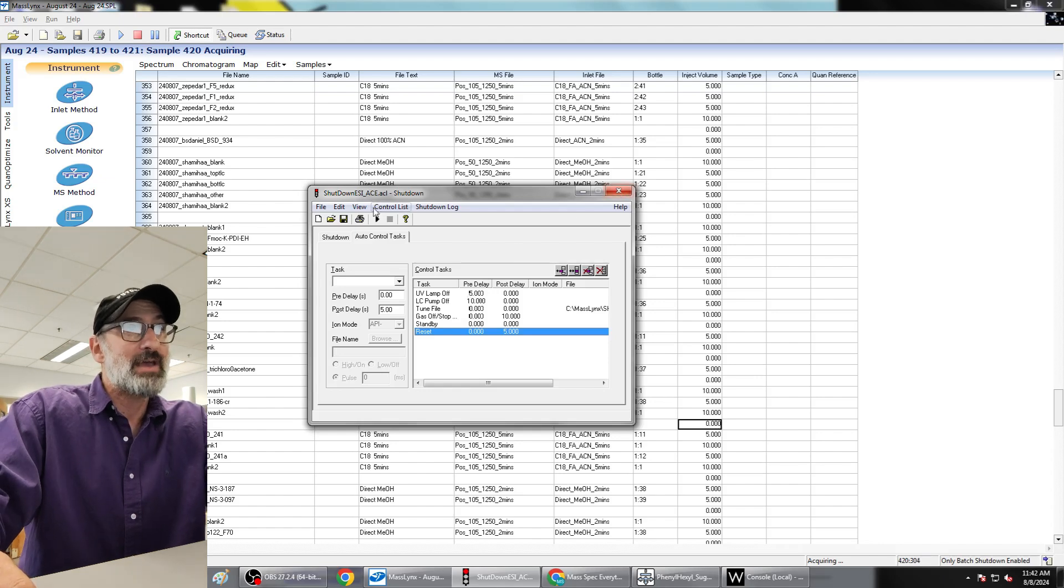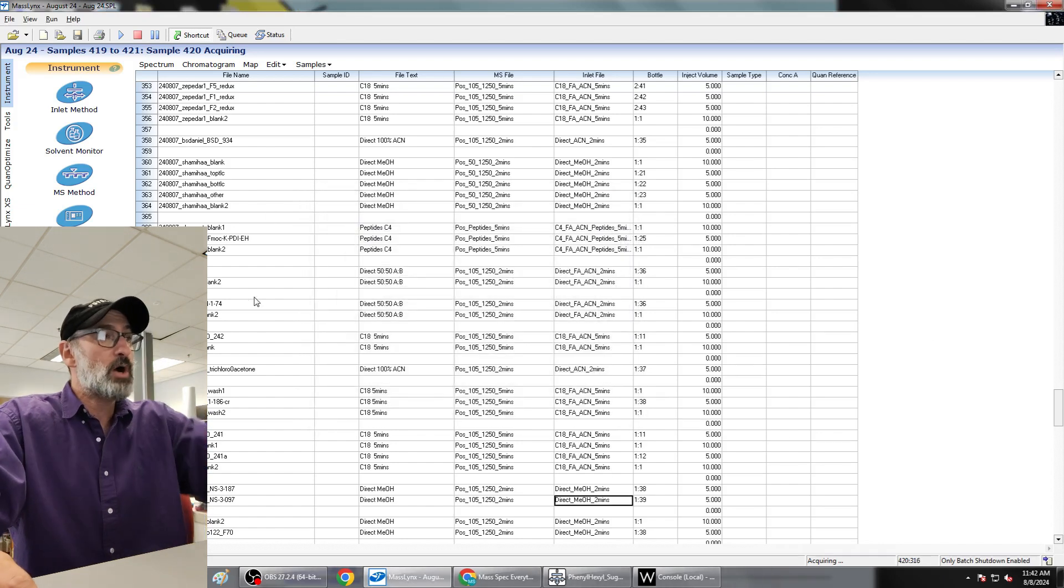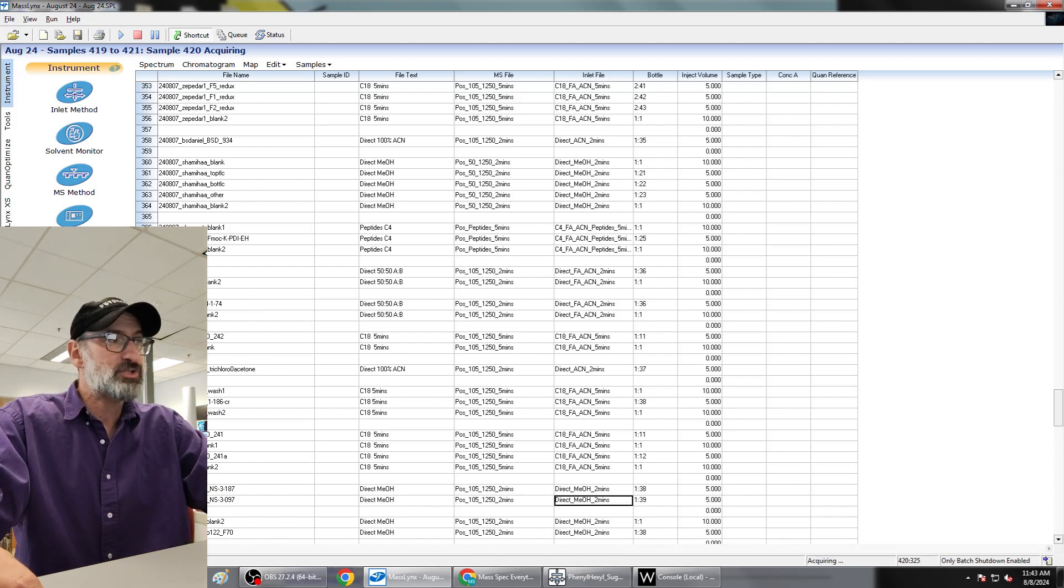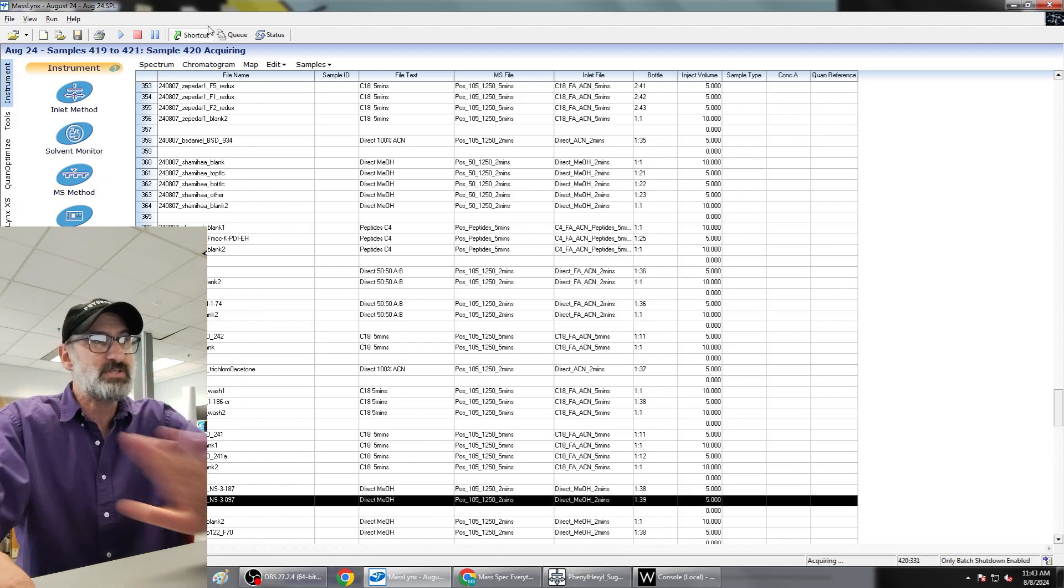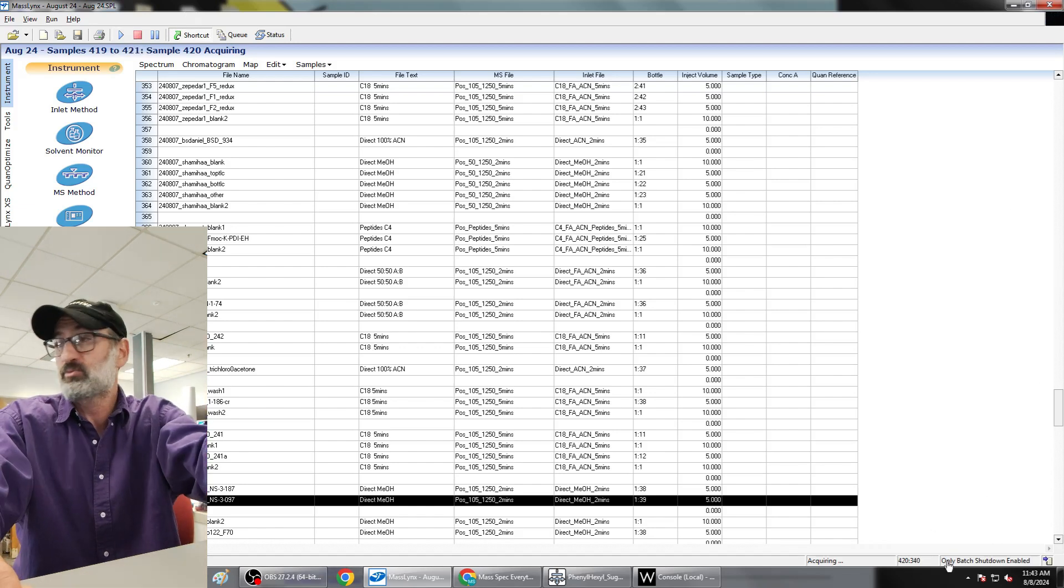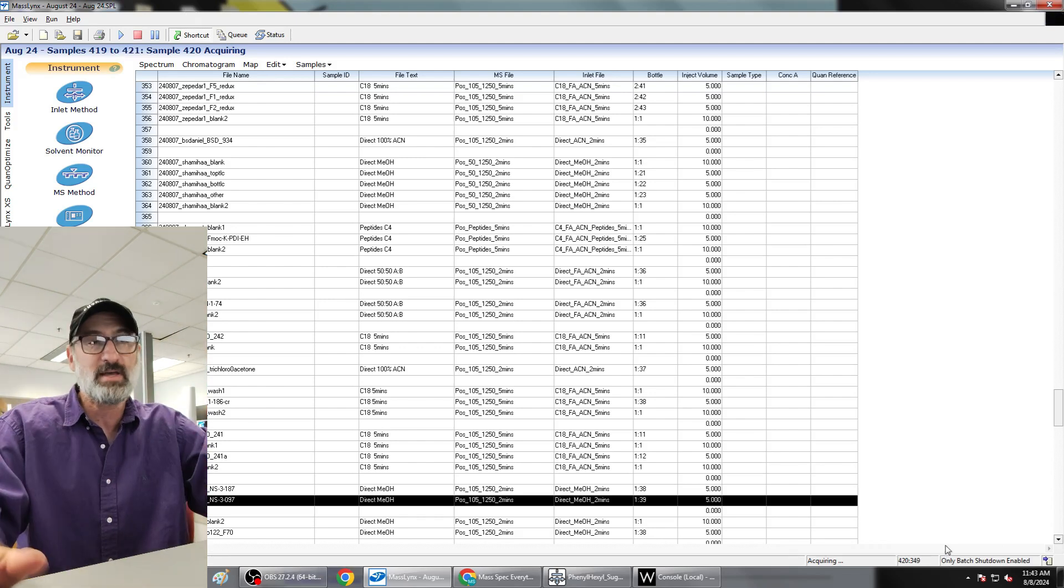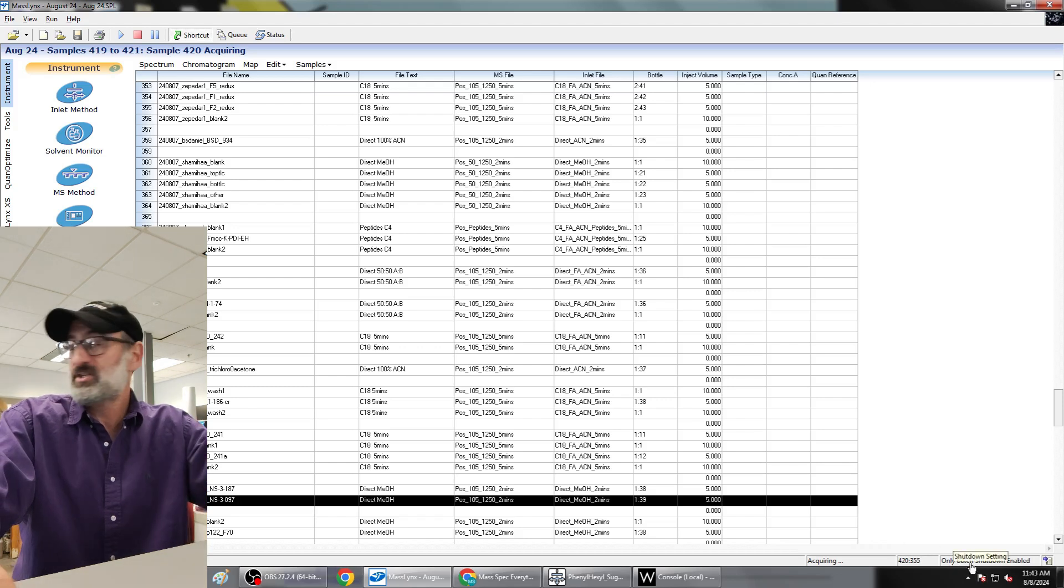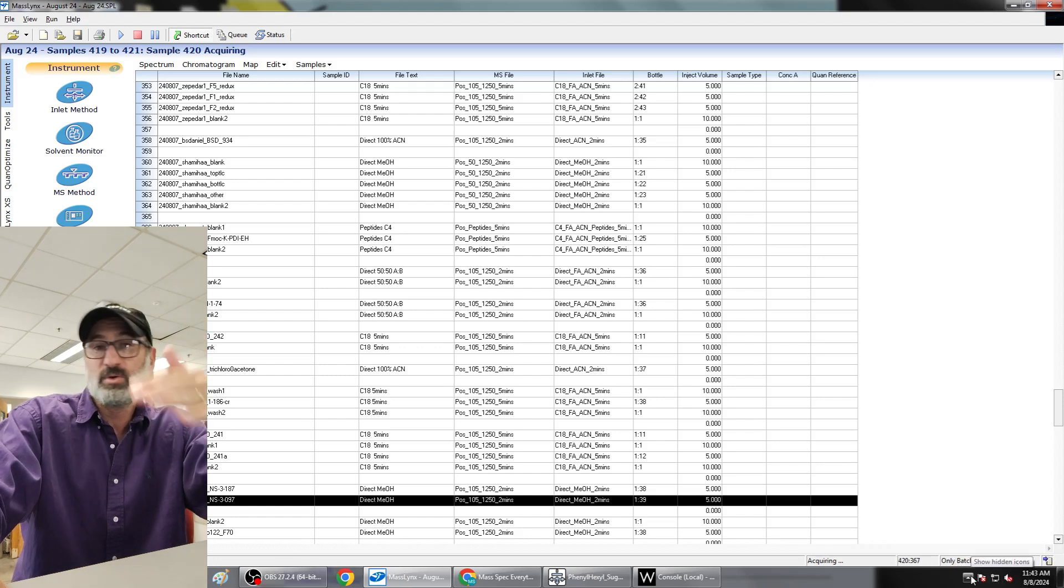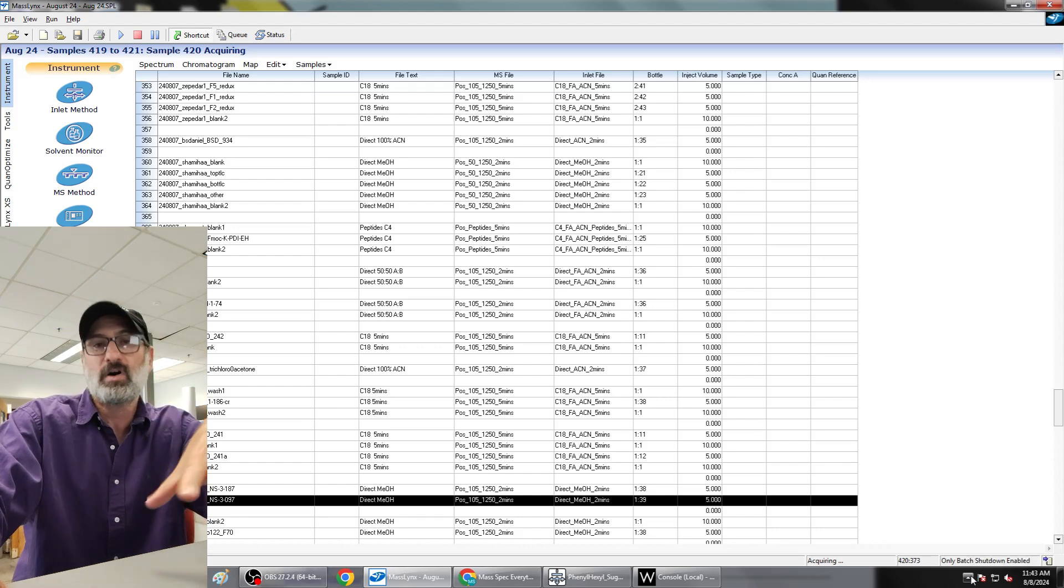So if you have all these things activated and set up properly, you just need to come over to an instrument. If the instrument says not ready and it's red, you can just come over to the instrument, write out everything as it needs to go, put your samples in the right position, and then just hit play and put it into the queue. And then you'll see in the bottom right-hand corner it'll say running startup. And it will turn itself on in the proper order so nobody messes up. And then after a run it finishes, you'll see a countdown clock. The countdown clock will be counting down from 15 minutes or 20 minutes where you put it at, and that will tell you when the instrument's going to turn itself off and it will automatically turn itself off.